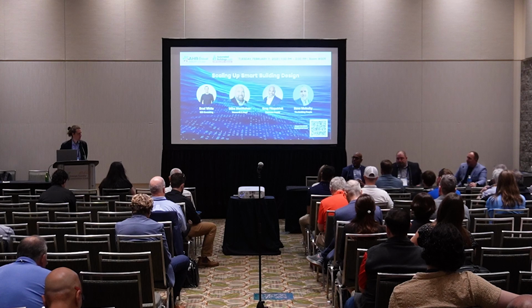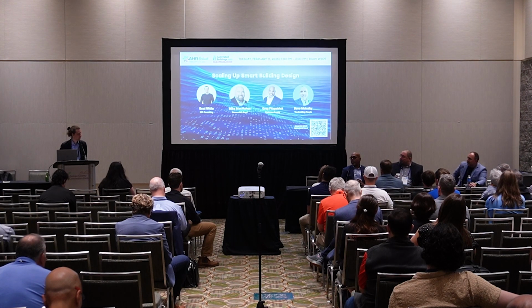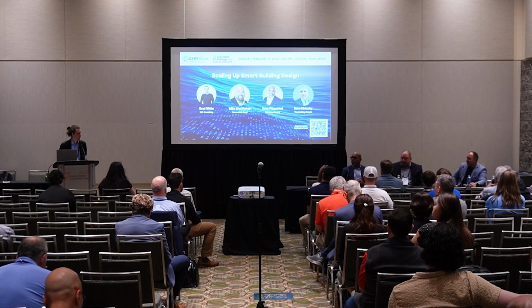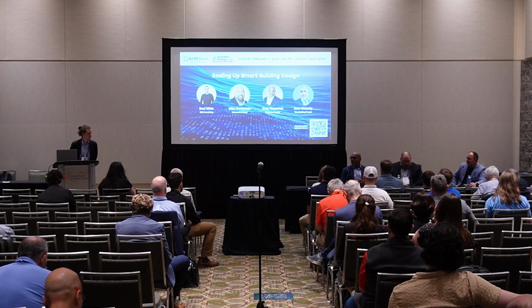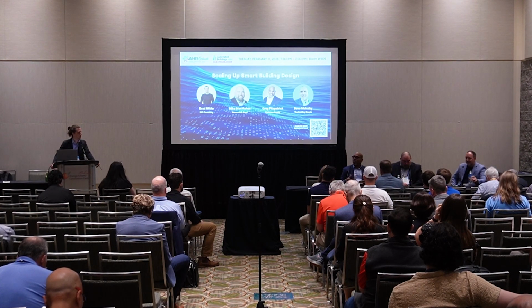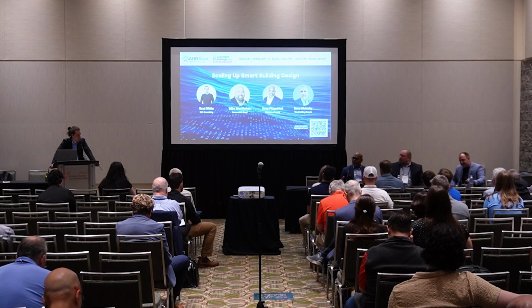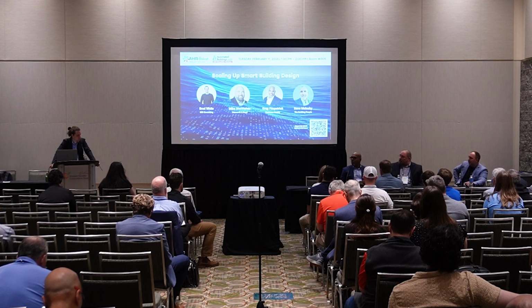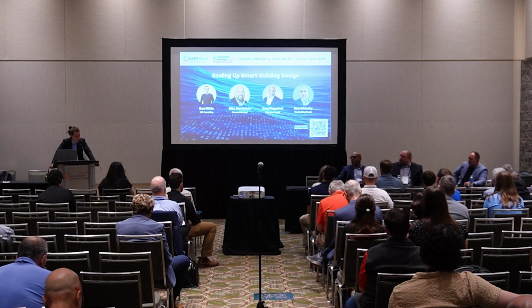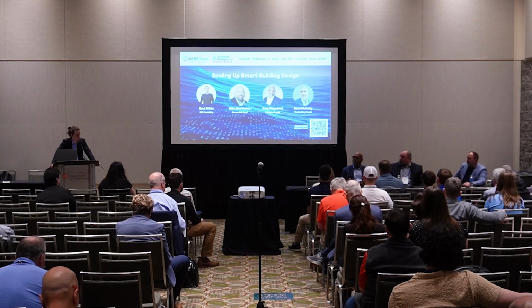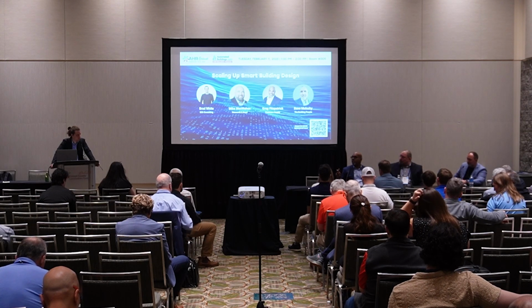One of the things we know is that 99% of buildings out there are going to have some type of remote access, right? Whether it's for just the owner or owner and service providers. And one thing that MEP firms need to know is what products are out there made for the facilities world or the BAS world that are zero trust remote access hardware and software solutions, to be able to at the very least put that in your specification as the quote-unquote firewall or the remote access strategy.